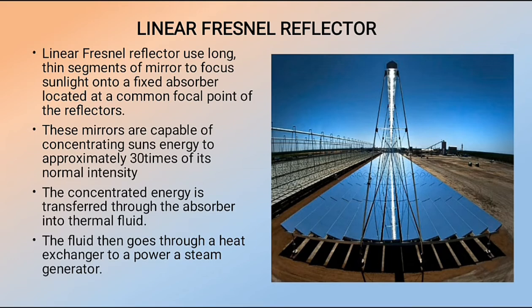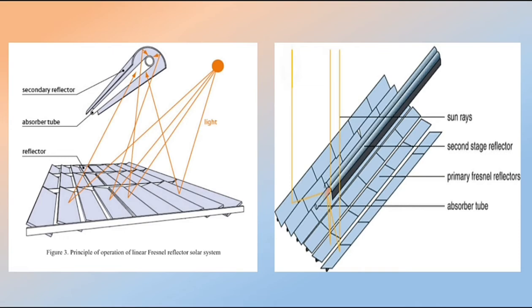The linear Fresnel reflector is similar to the power tower but uses a series of ground-based flat or curved mirrors to focus sunlight onto a fixed absorber located several meters above the mirror field. It is a single-axis tracking, line-focusing system. The absorber consists of long, selectively coated tubes through which flowing water is heated and sent to a steam generator to drive a turbine. A secondary reflector mirror refocuses sun's radiation onto the absorber to heat more water.